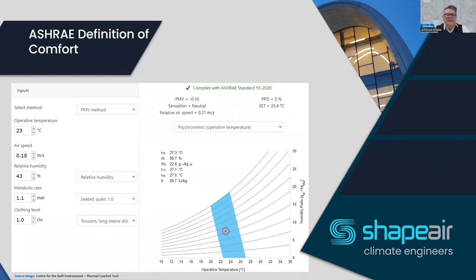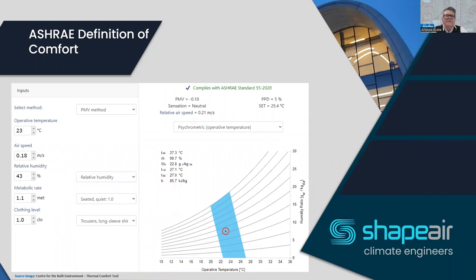ASHRAE's definition of comfort, calculated using the Berkeley calculator, looks like this: operative temperature of 23°C, airspeed of 0.18 m/s, relative humidity at 43%, metabolic rate of 1.1, and a CLO value of 1. That gives a PMV of -0.10 and a PPD of 5%, which is in line with Green Star for two green star credits — the best rating you can get.